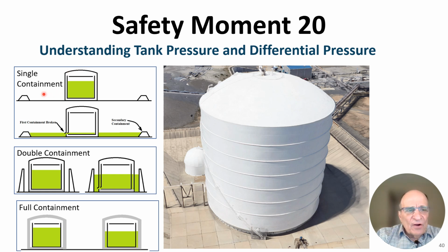And then a far distance away, you'll have a dike. When I say a far distance away, I'm not talking about 5 to 10 feet, but a significant distance away. You have a dike in case there were to be a spill. Let's say that inner tank were to rupture. Well, the outer tank, being carbon steel, would immediately rupture as well, and the LNG would be contained by this secondary containment. But this is called a single containment tank. A double containment tank is one where you bring the secondary containment real close to the tank. Maybe it's only 5 feet or 10 feet away from the tank, and it's really close.